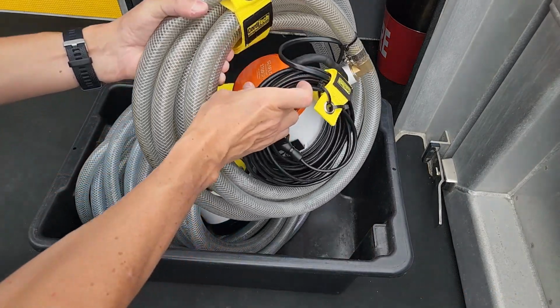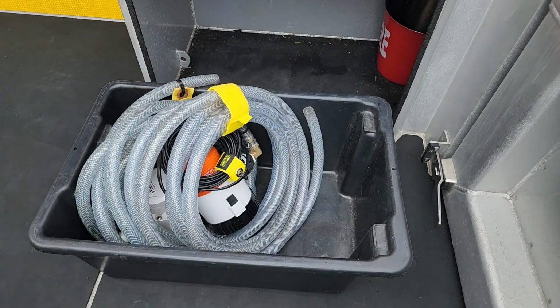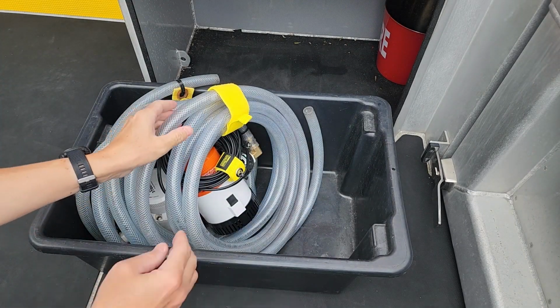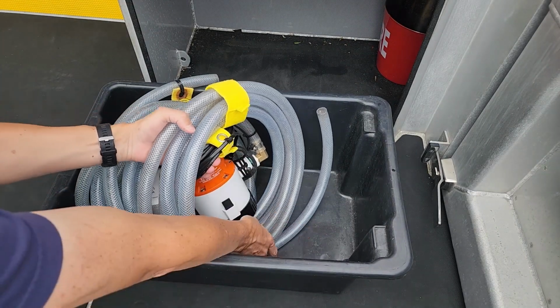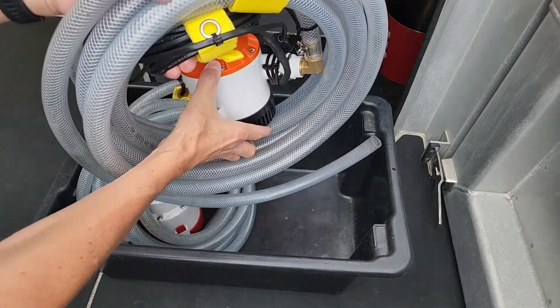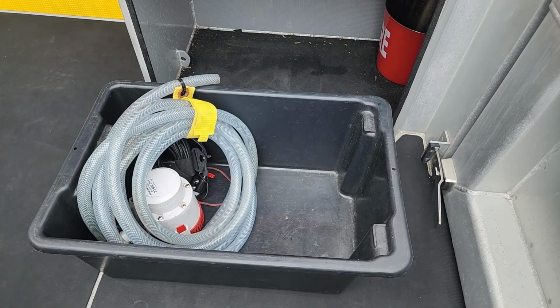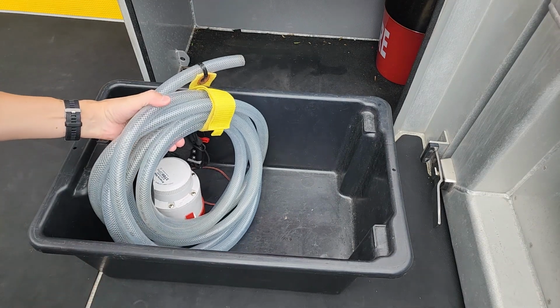The 3 pumps are taken out, one at a time. Be sure not to lift the pumps by the electrical cables, as that could damage the wiring. Each pump should be neatly stored with Velcro ties for the electrical cable, and a separate tie for the water hose.